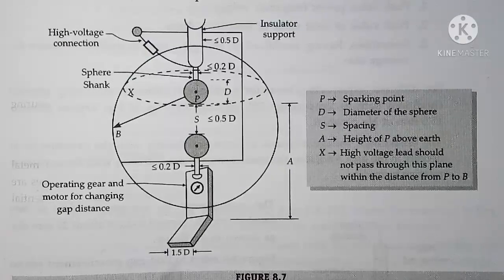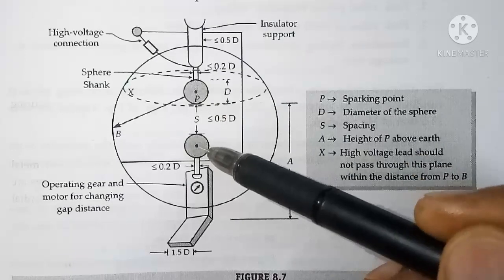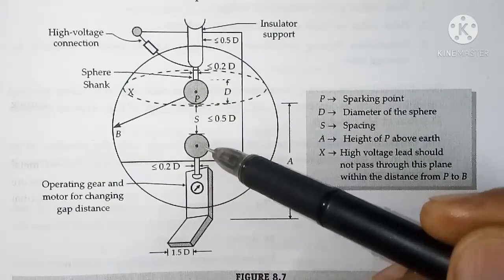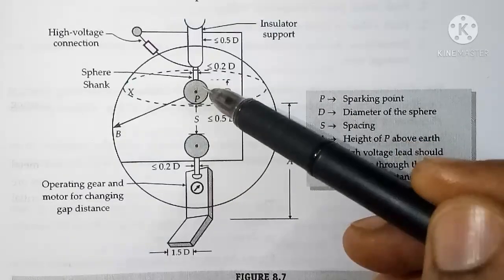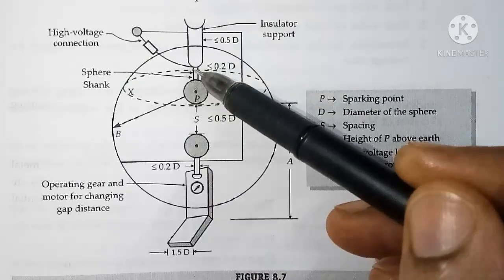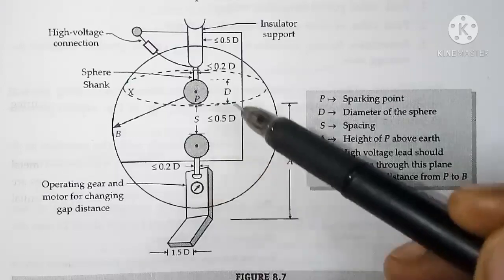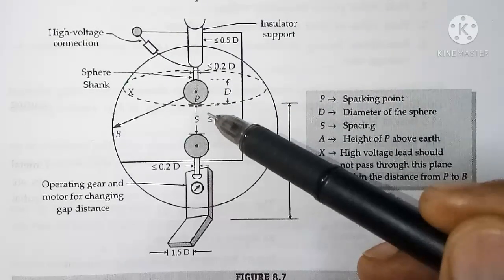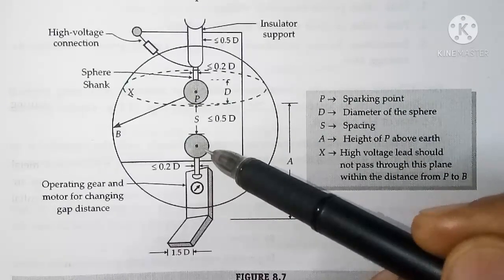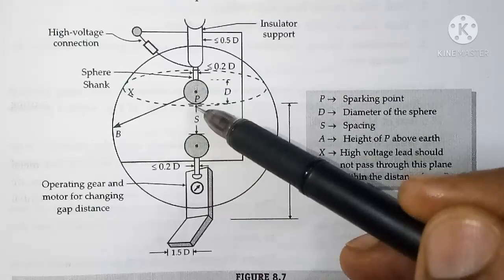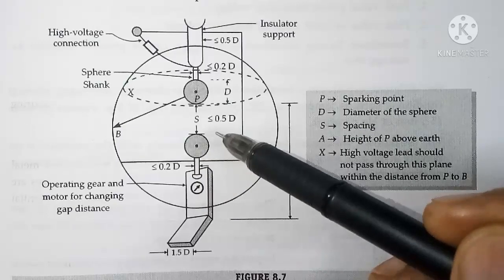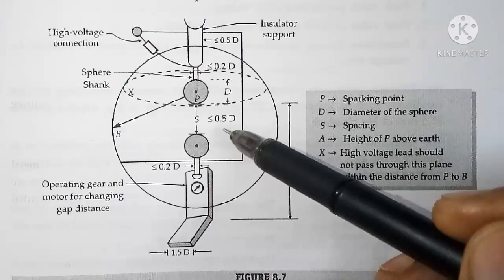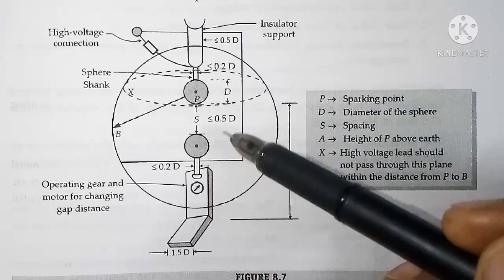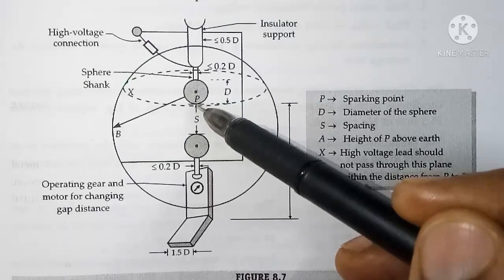Here what you see is the arrangement of sphere gap instrument used for measurement of high voltage. These shaded circles represent the spheres supported by insulating material. The rods that you see here are made up of conducting material and they are called the sphere shanks. D is the diameter of the sphere. Both spheres will have the same diameter. S is the spacing between the two spheres, and that will be less than or equal to half of the diameter of the sphere. P is the point at which the sparking takes place.